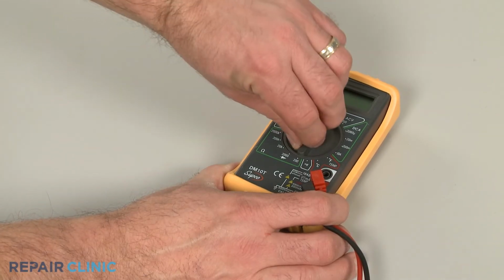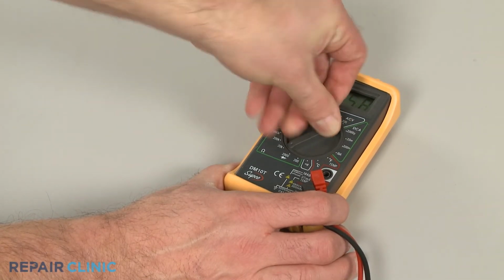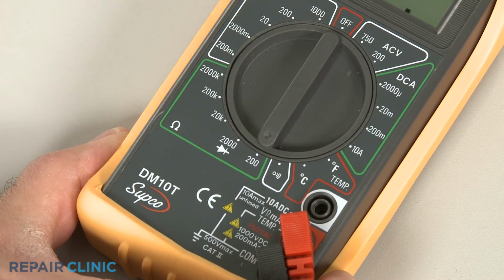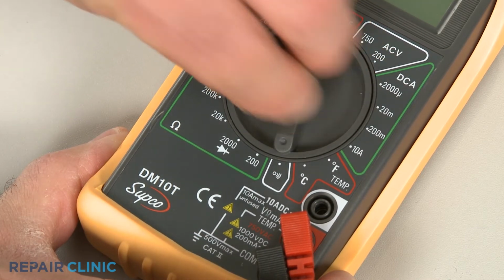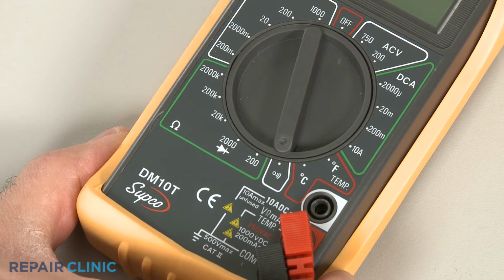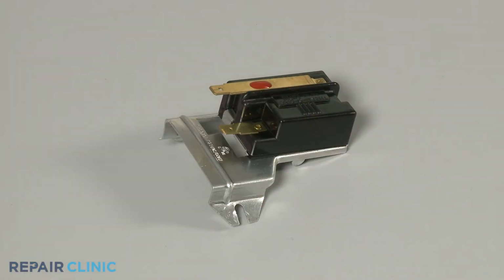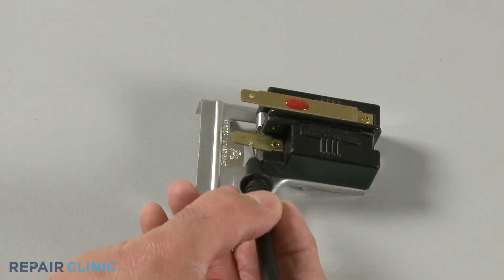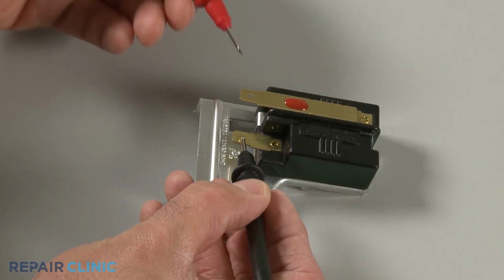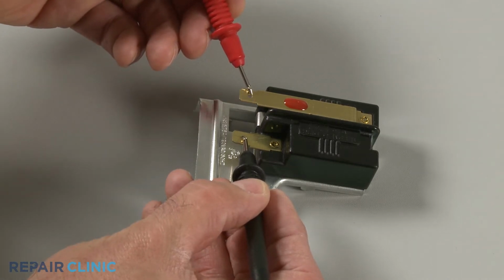When using a digital model, again rotate the dial to the lowest setting for ohms of resistance, or resistance with tone if your meter has this option. Before you begin, make sure the flame sensor has been removed or isolated from the appliance. Now, use a probe to touch one of the sensor's terminals, and the second probe to touch the other terminal.